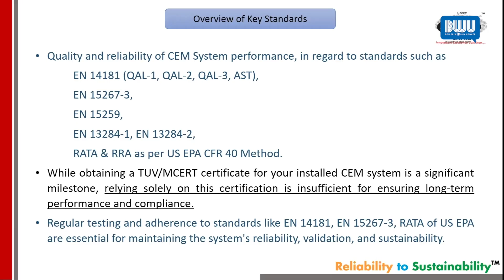Obtaining a TUV MCERTS certificate for your installed CEMS system is a significant milestone, because you spend a lot of money and you bought good equipment. But relying only on this certification is insufficient for ensuring long-term performance and compliance. Once certified doesn't mean lifetime certified. The standard says something different, which will come in the next slide. So regular testing and adherence to standards will give you reliability, validation, and sustainability. So, the importance of regular testing and certification.